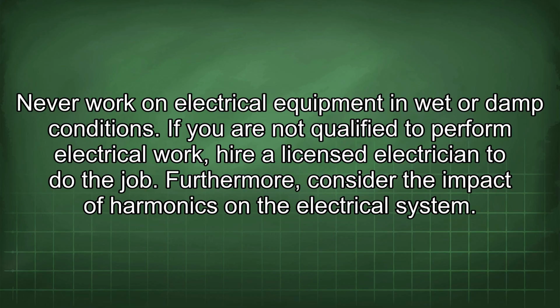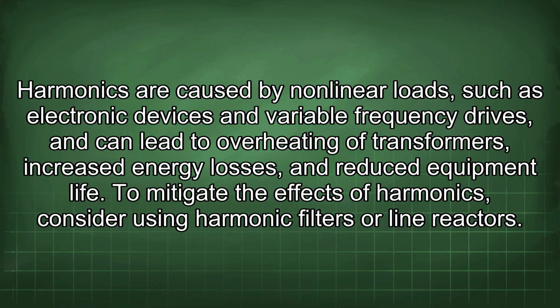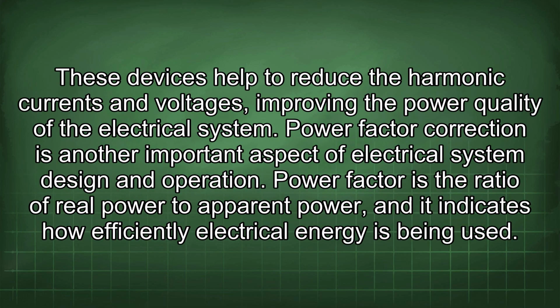Furthermore, consider the impact of harmonics on the electrical system. Harmonics are caused by nonlinear loads such as electronic devices and variable frequency drives, and can lead to overheating of transformers, increased energy losses, and reduced equipment life. To mitigate the effects of harmonics, consider using harmonic filters or line reactors. These devices help to reduce the harmonic currents and voltages, improving the power quality of the electrical system.